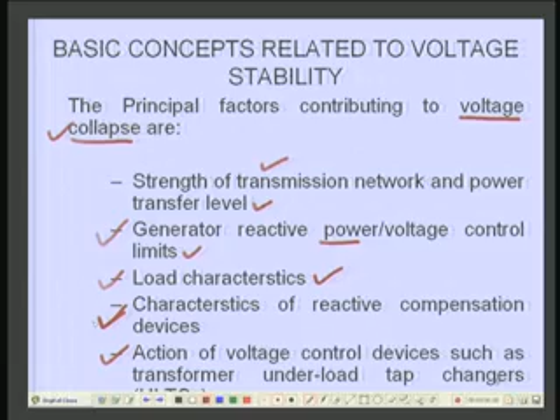Then one of the very important devices which affects voltage stability is the action of the underload tap changer of the transformers. In any power system we have the underload tap changers, we call them ULTC, or sometimes on load tap changers, and the function of the on load tap changer is to maintain the voltage at the load terminals. Many times it is seen, depending upon the load characteristic, that the ULTC may help in improving the stability, or sometimes it acts in an adverse way. We will discuss this effect of ULTC on voltage collapse phenomena separately.